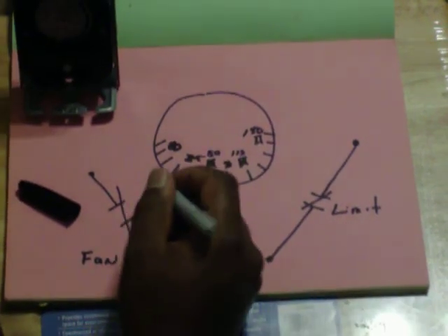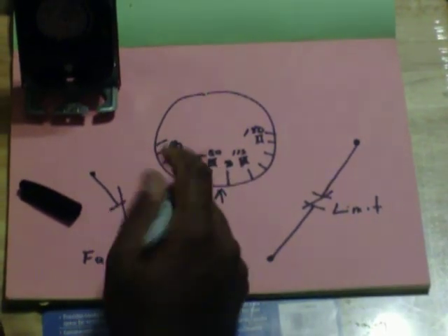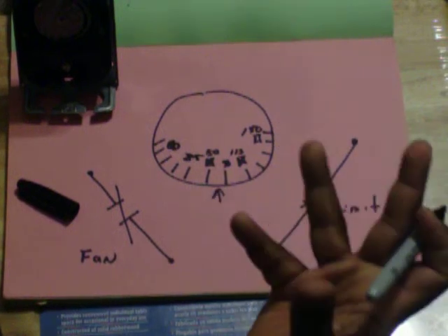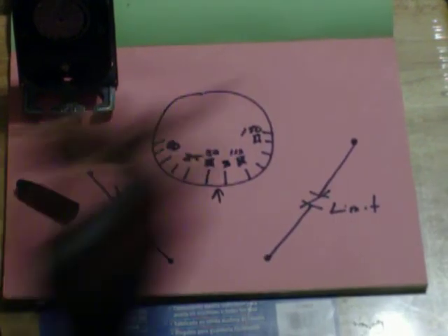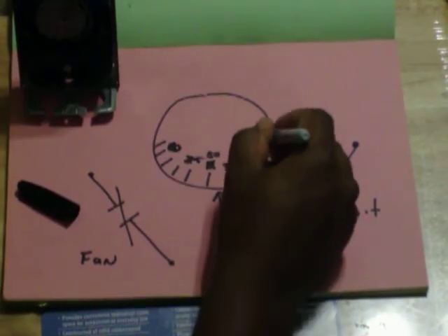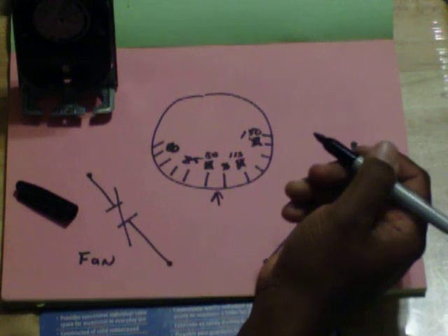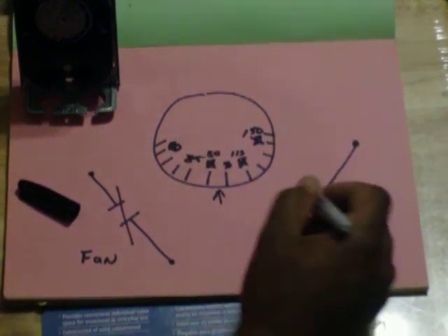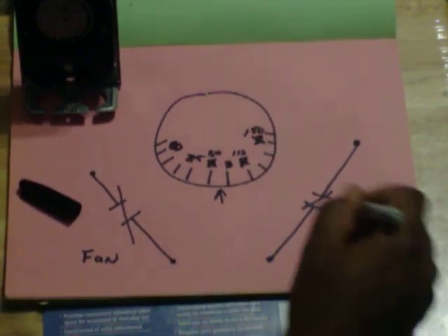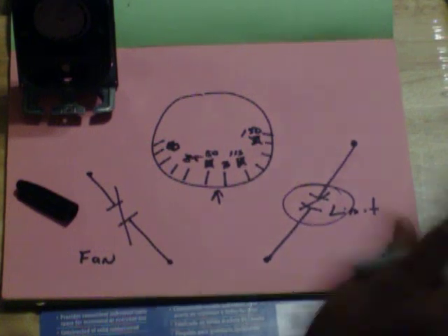If for whatever reason, let's say the disc doesn't close, or your fan's bad, your capacitor could be bad. For whatever reason, we don't get air flow. This would continue to spin, continue to spin, until we encounter the fan off pin. Which at that, I mean not fan off, your limit. Which at that point, open up your limit switch, kill everything.